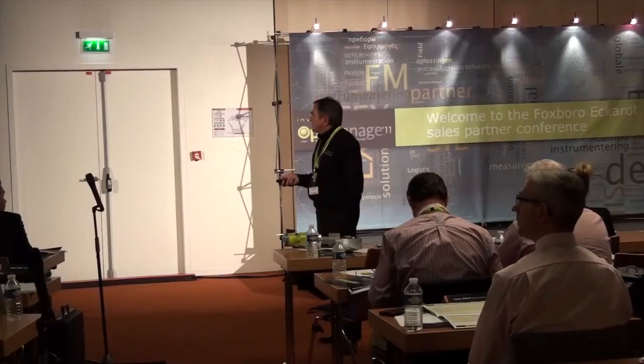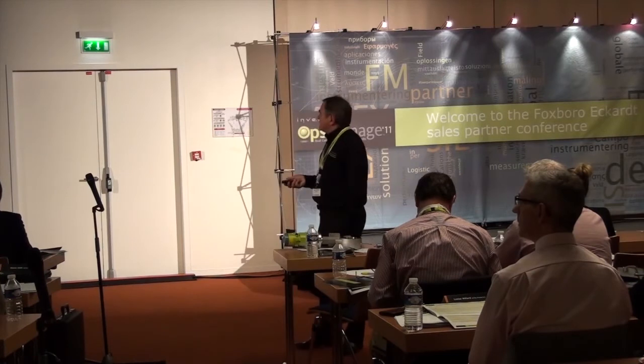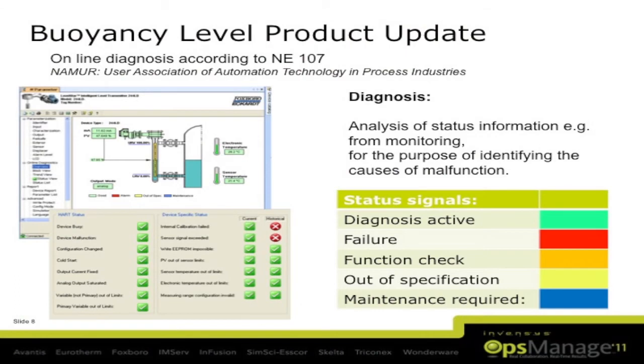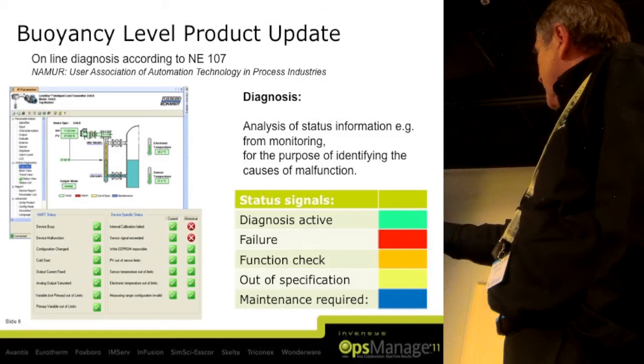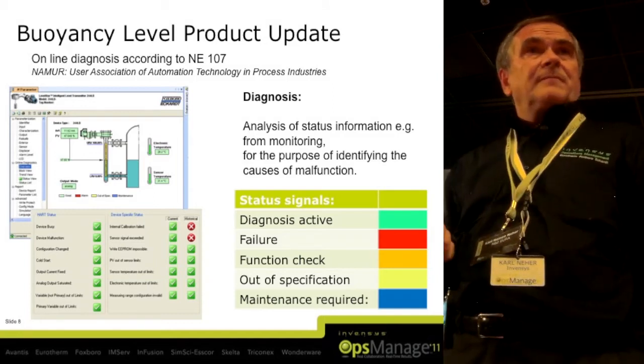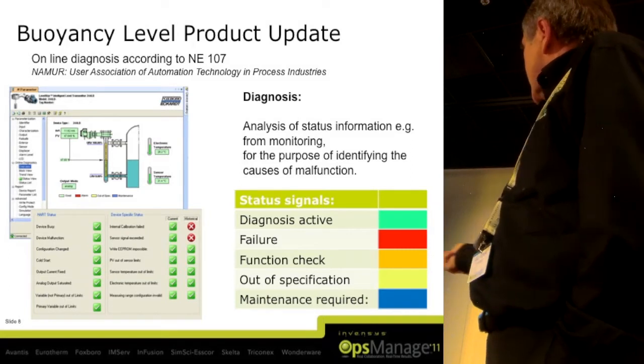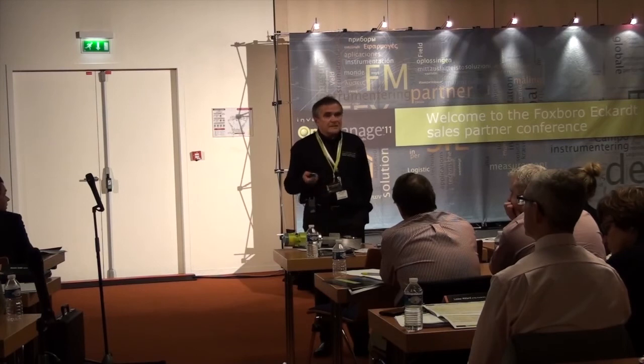And in this NAMUR standard, the status signals are standardized. Green means it is an active diagnostic and all is okay. So if this field is green, you know it's an active diagnostic parameter and it's okay. Failure is red, function check is orange, out of specification is yellow, and maintenance required is blue. This is the standard color in this NAMUR specification. We are using this in the fields here: maintenance, failure, and out of specification. On the buoyancy level transmitter, we did not use the orange field function check, so this instrument is working and it's not necessary to check the function.